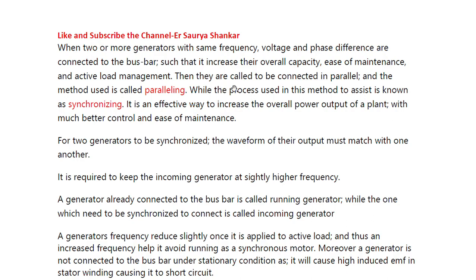When frequency, voltage, and phase difference are matched and two generators are connected to the bus bar, they are called to be connected in parallel, and the method is called paralleling. The process used to assist in this method is known as synchronizing — we are syncing two generators. It is an effective way to increase the overall power output of the plant with much better control and ease of maintenance.